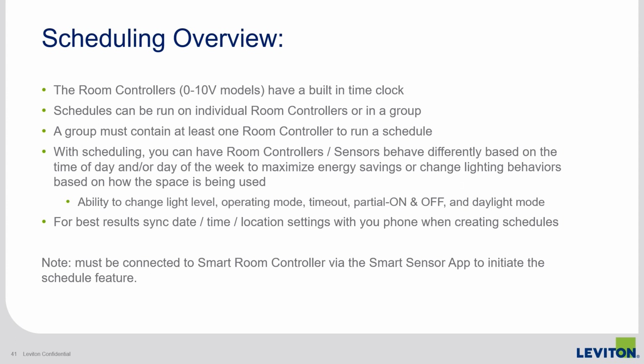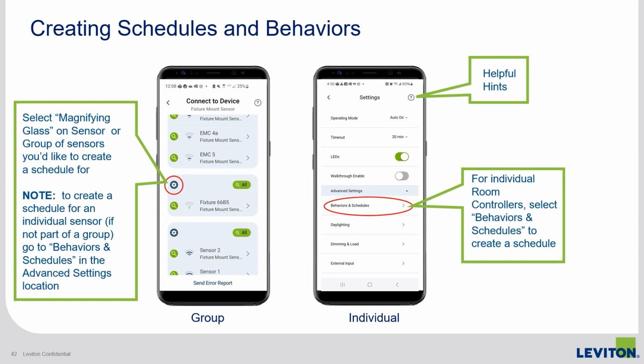With scheduling, you can change the light level, operating mode, timeout, partial on and off levels, and daylight mode based on the time or day of the week. If the group is mixed, you must be connected to a room controller in the group to create the schedule when you initially set up the schedule through the app. Next, we'll walk through how to create a schedule for a group of room controllers. The process for creating a schedule for an individual room controller is the same, except where you start the process from.